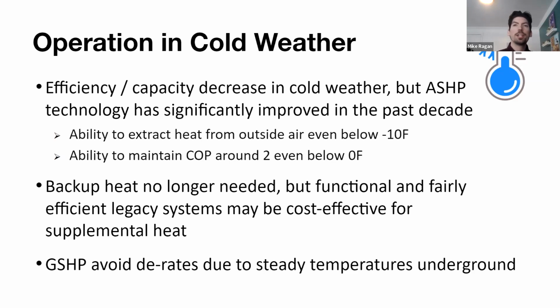So as the temperature outside goes down, the compressor is going to have to work harder in order to extract that heat. But even below 0 degrees, we're still achieving COPs over 2. So in that question, is a gas-fired boiler going to be more efficient at that temperature? Well, I don't know. From an energy efficiency standpoint, it wouldn't be. We would still get more efficiency out of the heat pump.